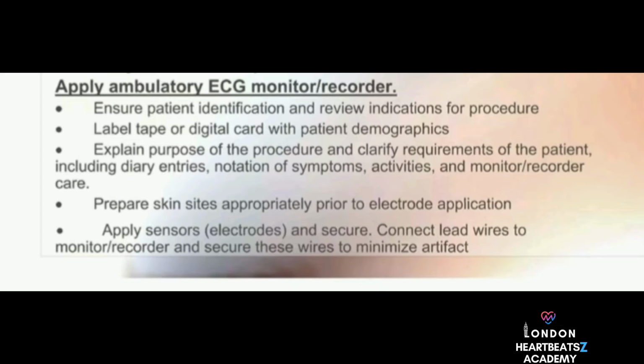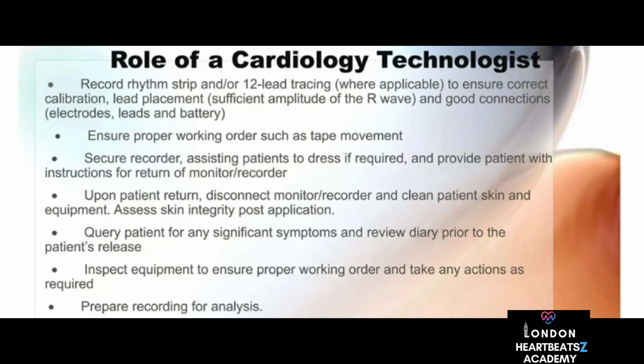Skin prep and electrode placement sounds simple, but probably crucial. Page 9 mentions this. Foundational. You need good signal quality. That means proper skin prep, maybe gentle abrasion, cleaning with alcohol to reduce electrical resistance, then careful electrode placement, securing the wires well, all to minimize artifact, electrical noise or interference. Muscle movement, poor contact. Yeah. It can mimic heart rhythm problems and makes the recording really hard, sometimes impossible, to interpret accurately. Bad prep, bad placement equals bad recording. Simple as that. Okay, so the monitor's on, what then?